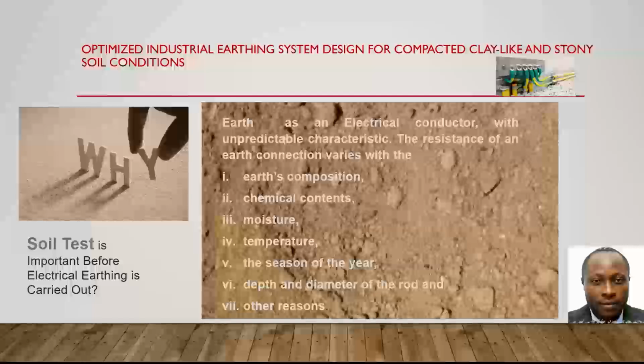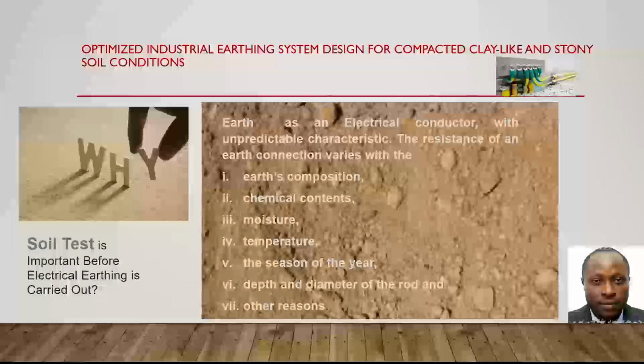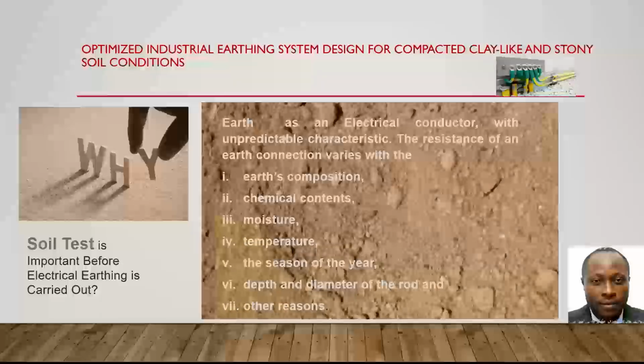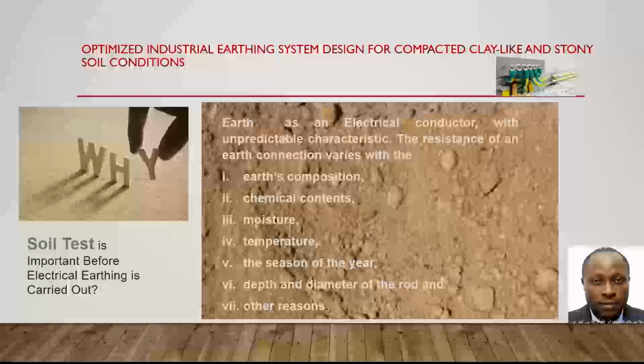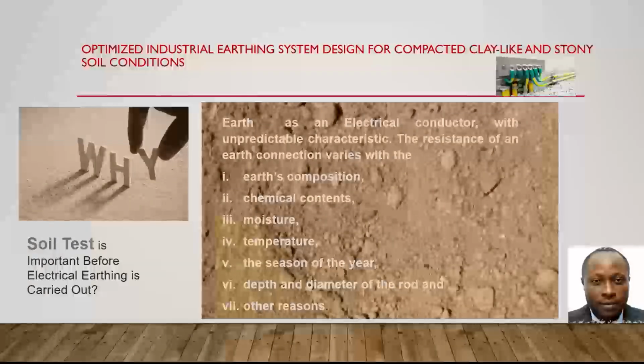The fault current that comes from any error or fault in the industry, or maybe lightning, needs somewhere to go. Like in chemistry or biology, gases move from a region of higher concentration to a region of lower concentration, so also current moves from the source to a part with less resistance to its flow, that is where it will go. This land, this soil, this earth, is abundant around us and ready to accommodate all this excess current. Why do we need to depend on earth for this? If you look at our equipment in industry, a panel, an electrical panel, or a motor of maybe 15 horsepower driving a conversion, or a chiller or compressor in industry...